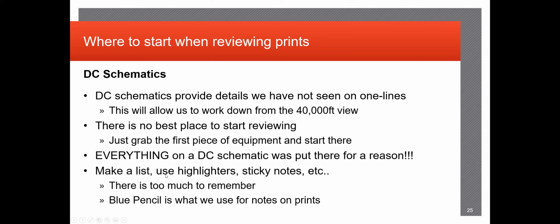My way I always remembered to do stuff was blue pencil for wiring checks. You're just pretty much checking stuff off along the way. And then once you highlight stuff, that means you have functionally verified it in every way, shape, and form, that it is going to properly function per the design intent. So your highlighting is the last leg before you give it back to the client and say, yep, it's good to go. So if you didn't test something and you highlighted it, that's on you. That's not good.